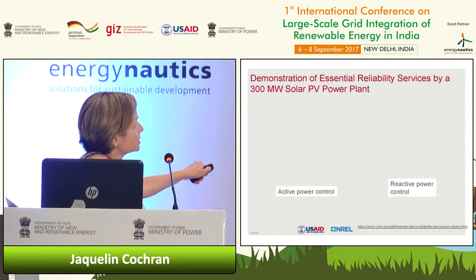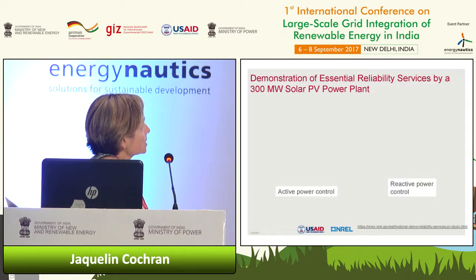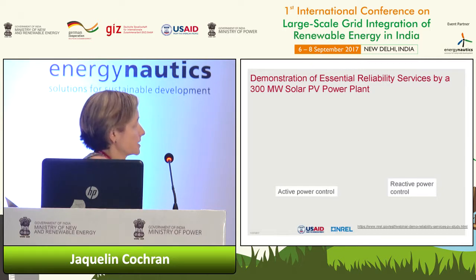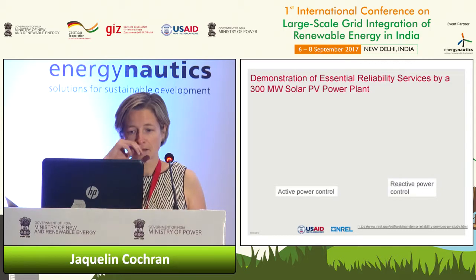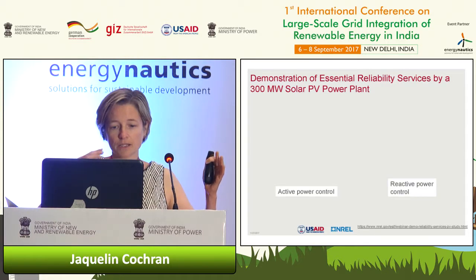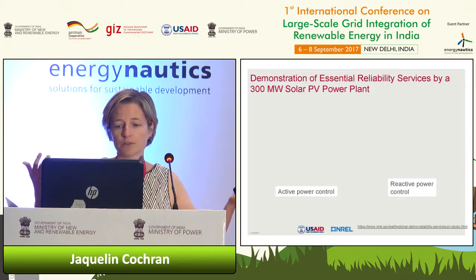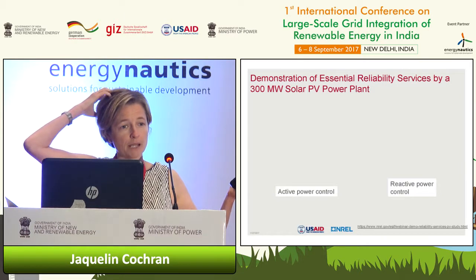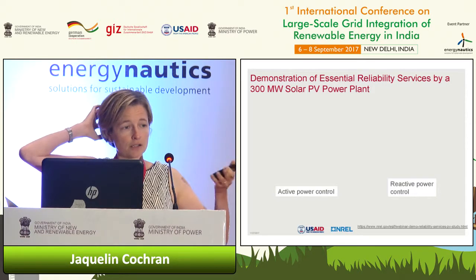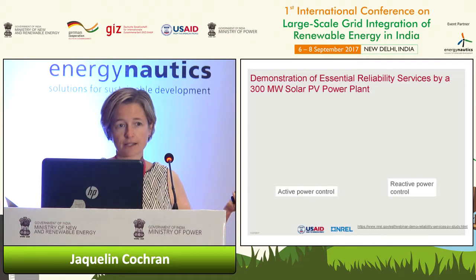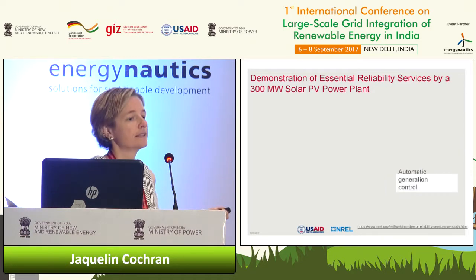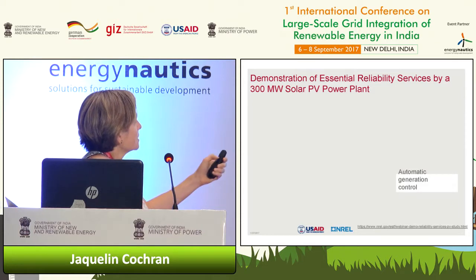They are also able to use this power plant to consume and inject reactive power. You can see here as it goes up and down, and this is the impact of that on the voltage and on the active power of doing these reactive power controls. So they're able to really highly control this power plant. They're even able to provide reactive power at night by drawing on the current that's available on the system, so acting like a STATCOM.